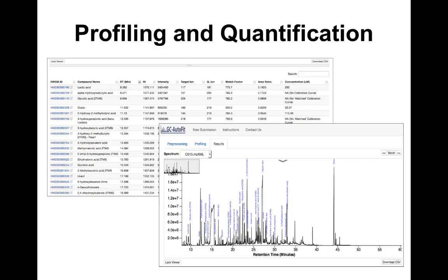So it uses essentially the same viewing tool that is used in Basel. You see a little spectrum in the upper left corner, which is the full spectrum, and then you'll see peaks, which you can click on to identify which compound is which. There's a comma-separated value file, which indicates the compound name, its retention time, the intensity, and calculated concentration.